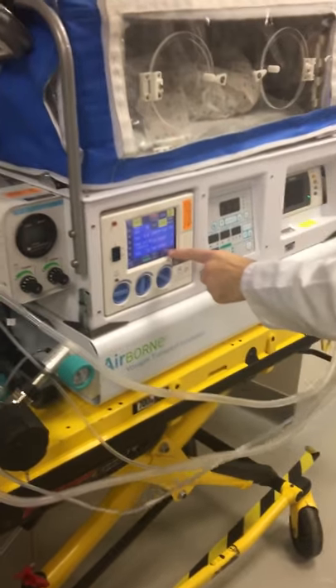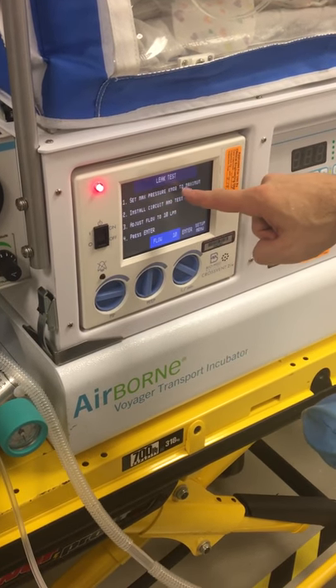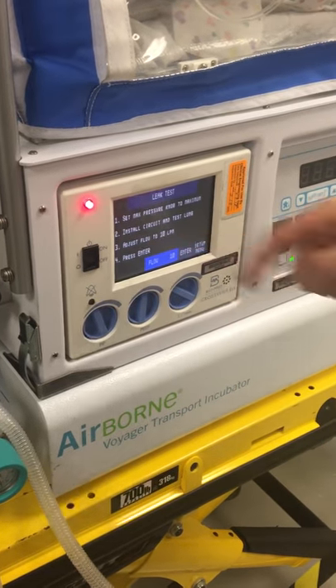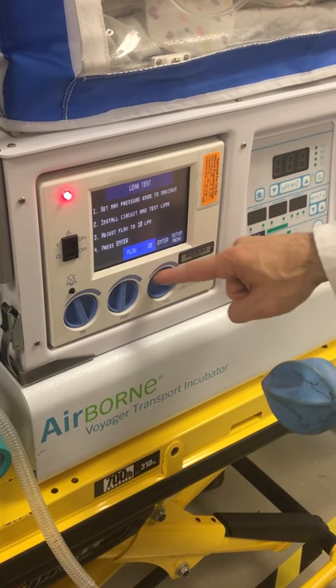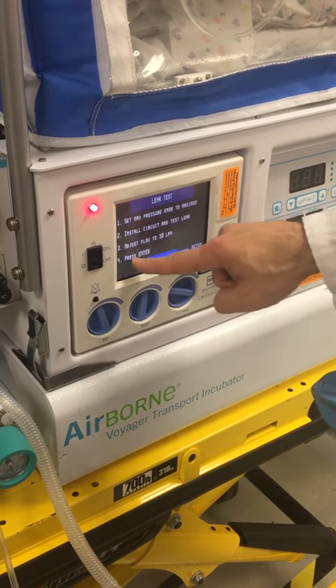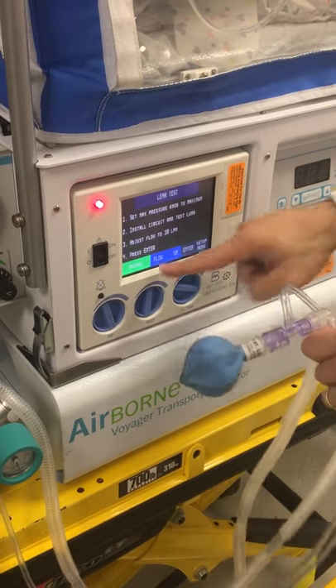We have our test lung in here and we're going to turn on the cross vent. When we do that we'll hit set up right here, and then we're going to do a leak test. Set the max pressure knob to maximum — this is our peak inspiratory pressure knob. Install the circuit and test lung. Adjust flow to 10 liters per minute using this flow knob right here, then press enter and it's going to run a leak test. Passed.